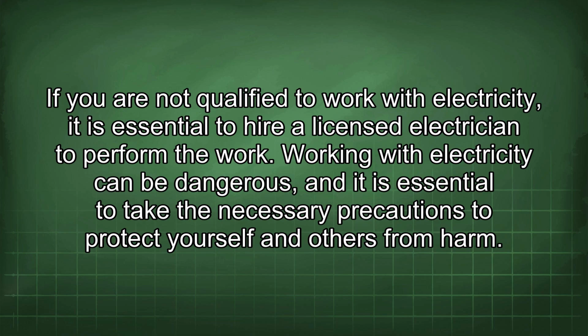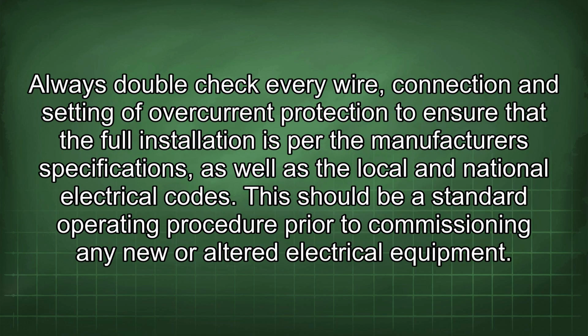Always double-check every wire, connection and setting of overcurrent protection to ensure that the full installation is per the manufacturer's specifications as well as the local and national electrical codes. This should be a standard operating procedure prior to commissioning any new or altered electrical equipment.